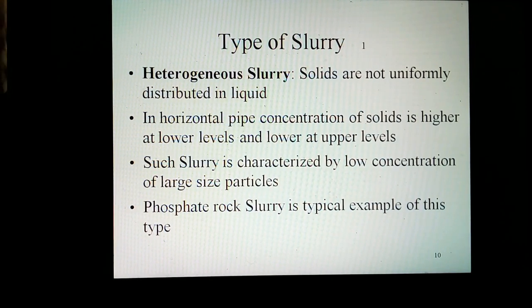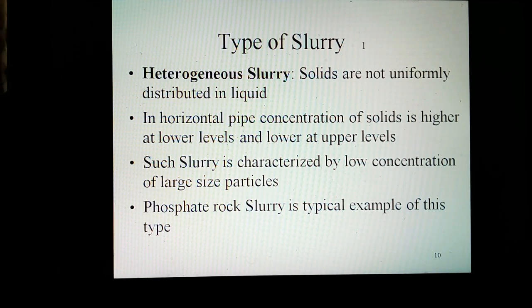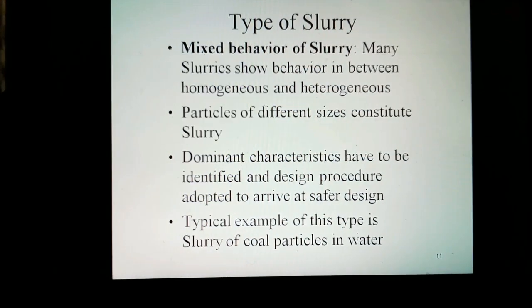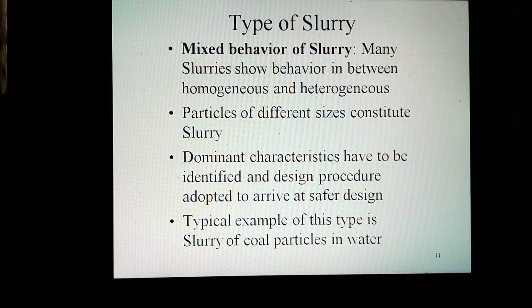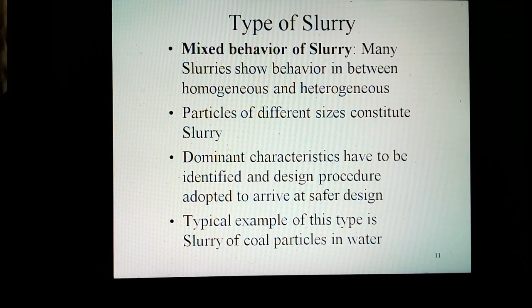In heterogeneous slurry, the solids are not uniformly distributed in the liquid. In a horizontal pipe, the concentration of solids is higher at lower levels and lower at upper levels. Such slurry is characterized by low concentration of large-sized particles. Phosphate rock slurry is a typical example of this type. Many slurries encountered in industry may show behavior in between homogeneous and heterogeneous. This would be more so when particles of different sizes constitute a slurry. In such a situation, dominant characteristics have to be identified and the design procedure adopted to arrive at a safer design. A typical example of this type is a slurry of coal particles in water.